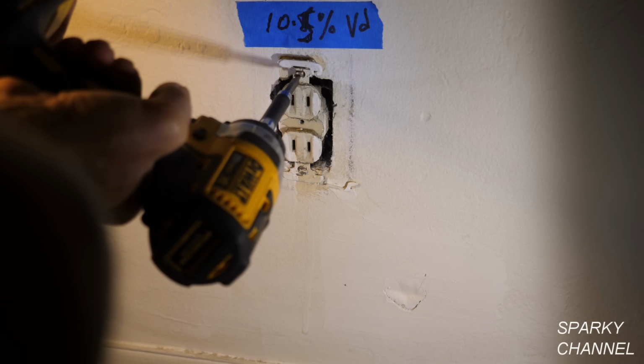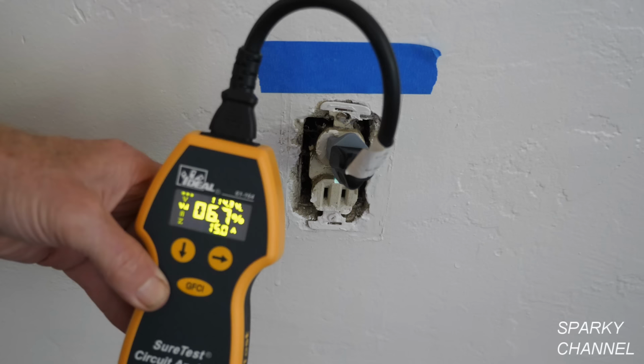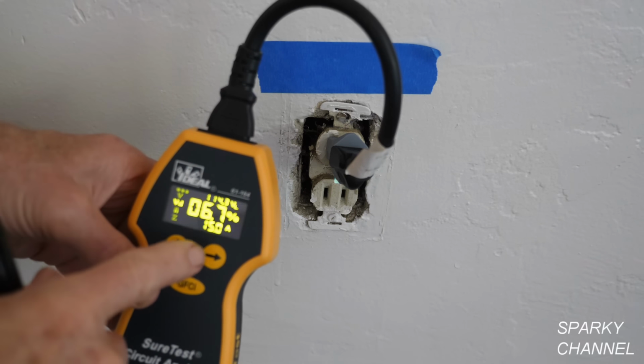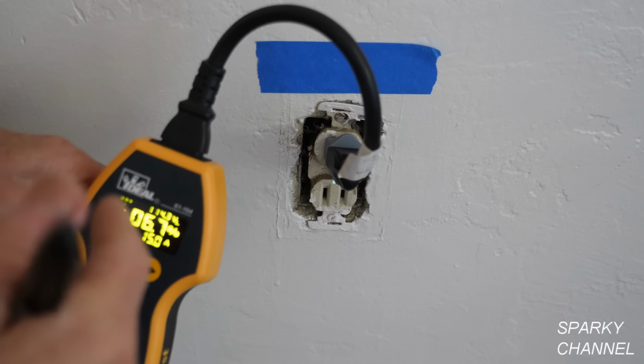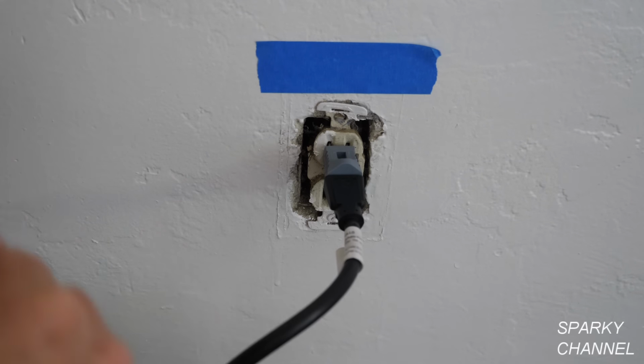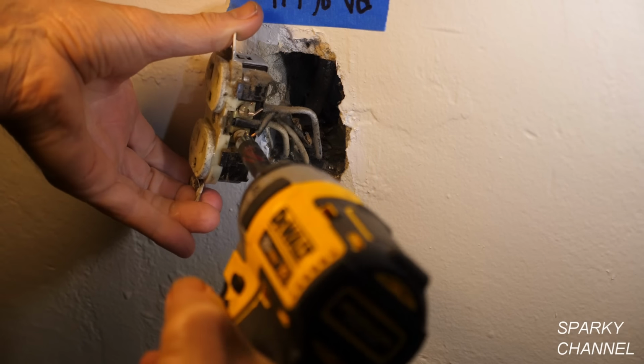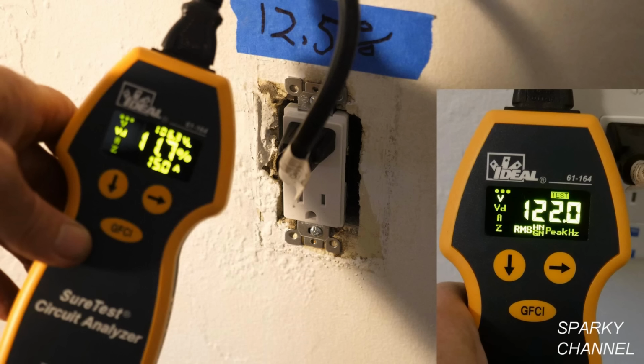In conclusion, I think this was an excellent project with the benefits of getting rid of the annoying 2-prong receptacles, as well as a couple of non-code old 3-prong receptacles. The voltage drop at 15 amps load was reduced for every replaced receptacle, and the old backstab receptacles were eliminated.